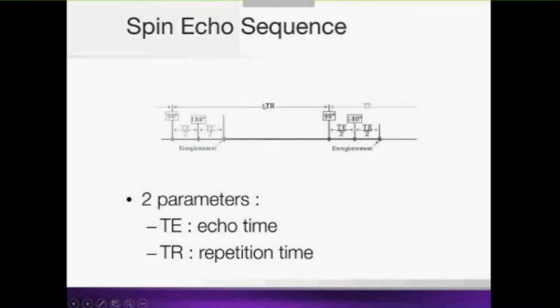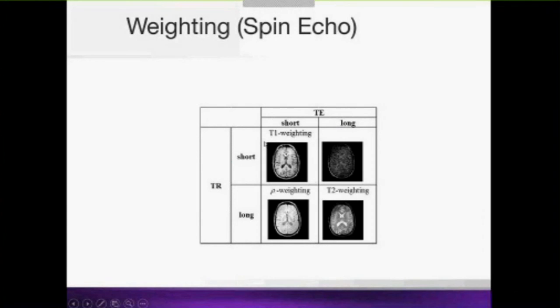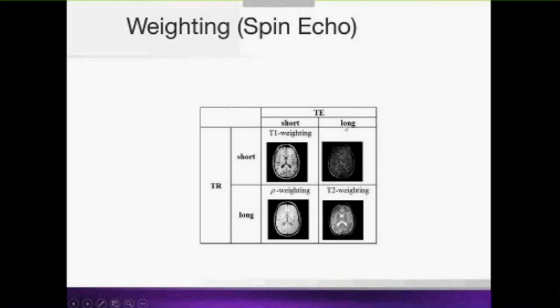This sequence of 90 degrees followed by 180 degrees is separated by a time called the TR, the repetition time. The time from the excitation to the echo is called the TE, the echo time. Both TE and TR can be set on the scanner. Simply by changing TE and TR — making them shorter or longer — you can obtain different contrast weightings. With a short TE and short TR you get T1 weighting: white matter appears bright, gray matter gray, and CSF dark. With a short TE and long TR you get proton density weighting, which is less commonly used in clinical practice today.